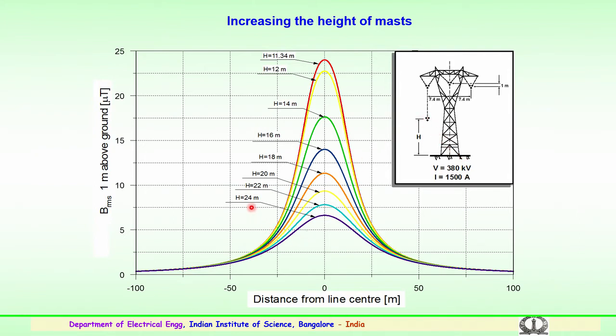So the height, h, is considered from 11.34 meters to 12, 14 and up to 24 meters. You can very clearly see as the height decreases, the magnetic field increases. You can see the values, typically for 11 meter clearance height with the conductor being charged at 1500 amps for a voltage level of a 380 kV system, the magnetic field could be somewhere around 23 to 24 micro tesla. As the distance increases, the magnetic field gets reduced. You can see for 14 meter, 16, 20, and so on. At a height of 24 meters, you can see the reduction from 23 micro tesla to approximately 6 to 7 micro tesla.